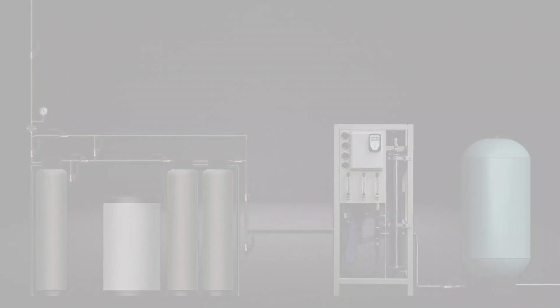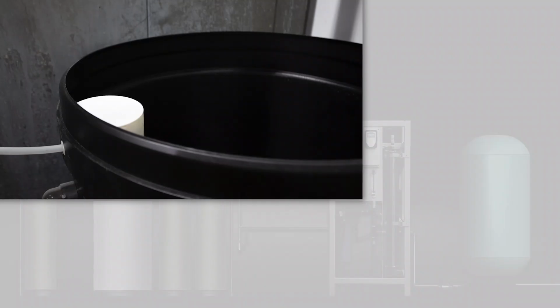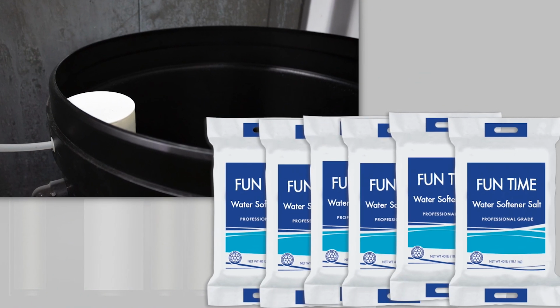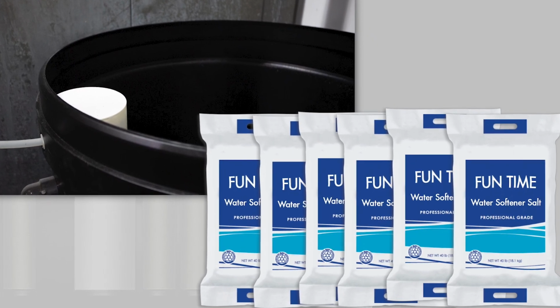And water is one of those key things. If you shift to having cleaner water, you maybe shift the maintenance to the water treatment equipment instead. I can maintain a water softener. I refill it with salt. Then that makes it easier and not as hard on the humidifier. I've just shifted the maintenance and what I have to do.